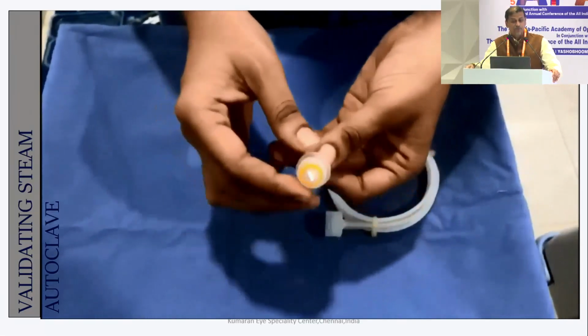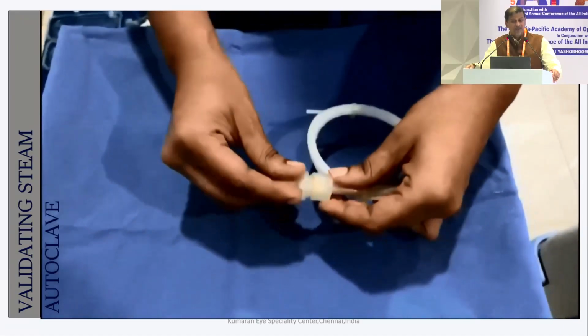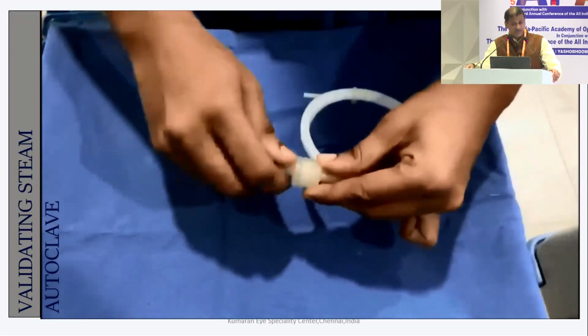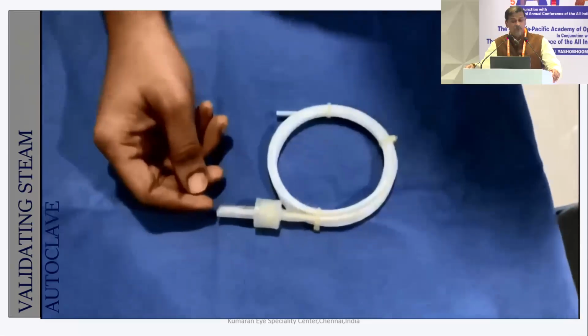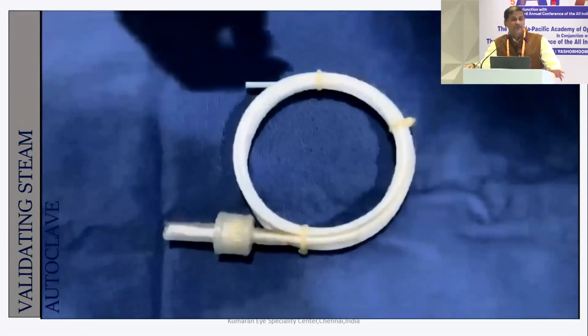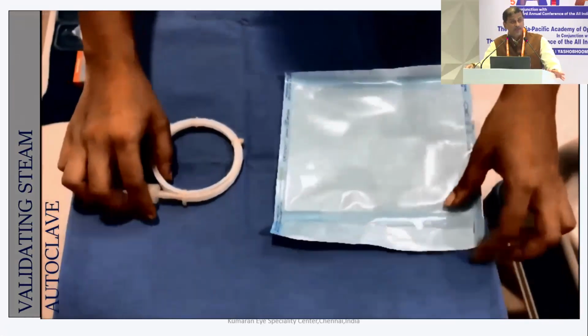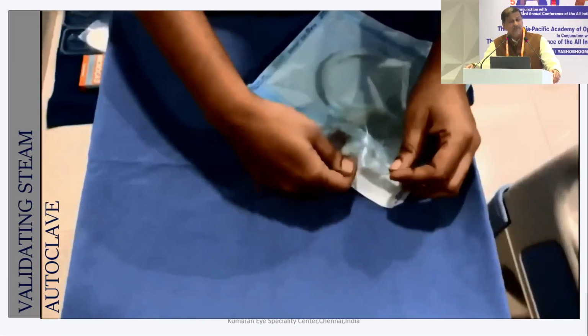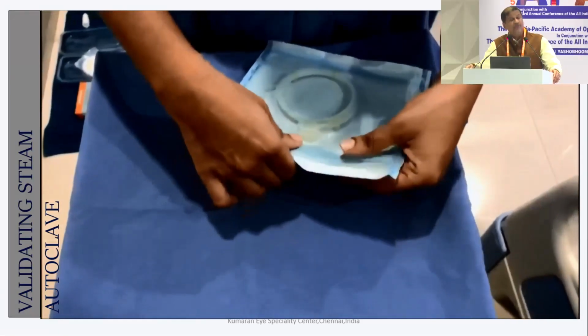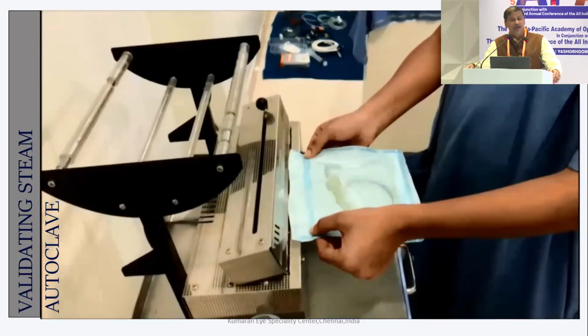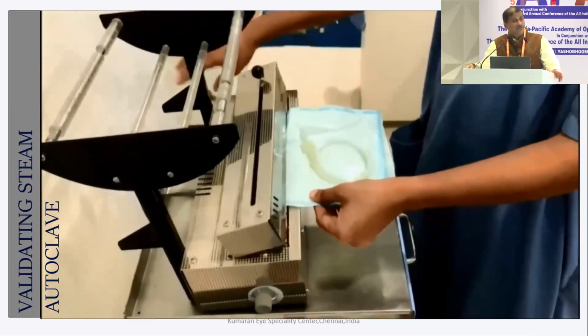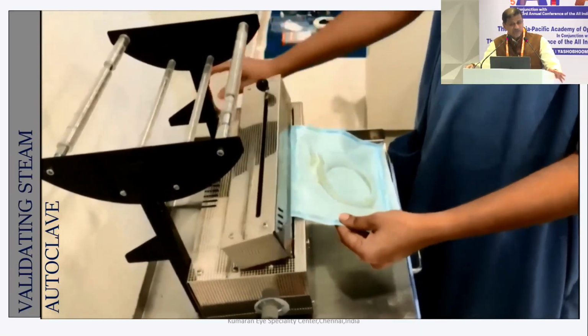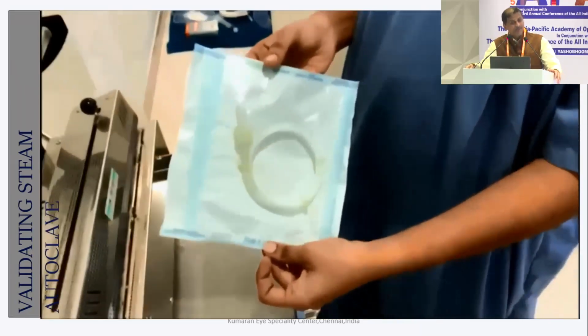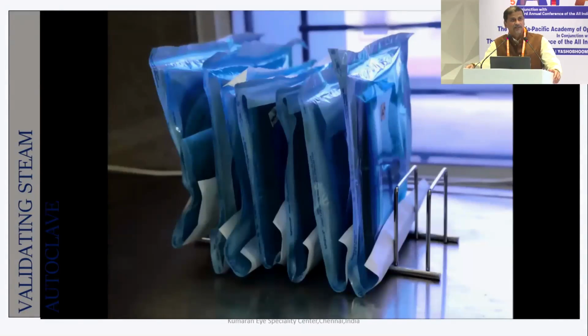The strip is folded as shown here. The way you insert the strip inside the holder is very important. So this basically works on the principle that your autoclave is able to remove the air inside this 1 meter, 0.1 millimeter lumen tube, and then the steam is able to reach the other end of the holder. So this is also packed the same way you pack your instruments and placed along with your sterilizing goods or your instruments.